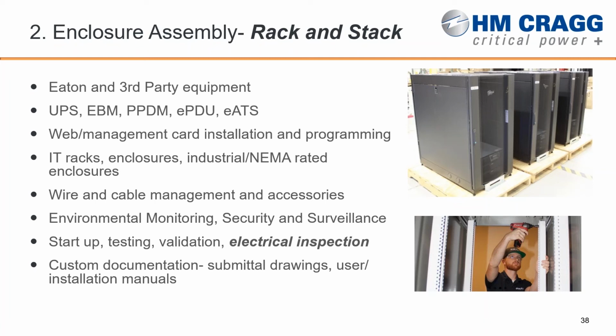But here's the other thing we'll do when we do these assemblies: we'll actually start the UPS up. So we connect the battery, power the unit up, run it through its startup procedure, whatever Eaton's specific startup procedure is. We can do some load testing to validate that everything is working the way it's supposed to.